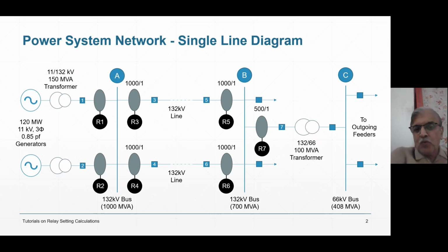But that you can't just do because if there is a fault on lower line, that is another line AB, then the fault current will be flowing from R3, R5, R6 and fault. Then you would say that time of operation of R5 should be more than R6. That is just not possible. Therefore, time of operation, or so to say TMS of R5 and R6, which are located on the same bus, are always same. And if you want only one relay to operate, then R5 and R6 have to be added with one more discriminative sense, that is the direction.